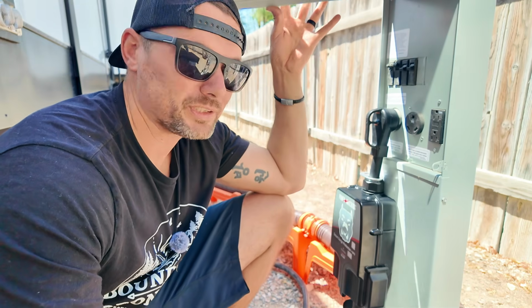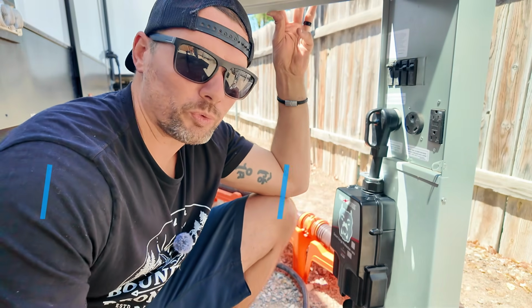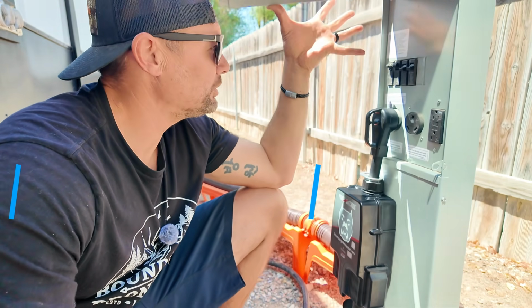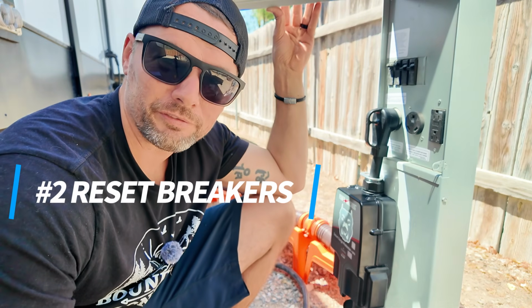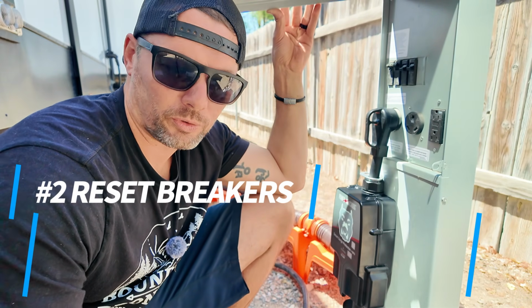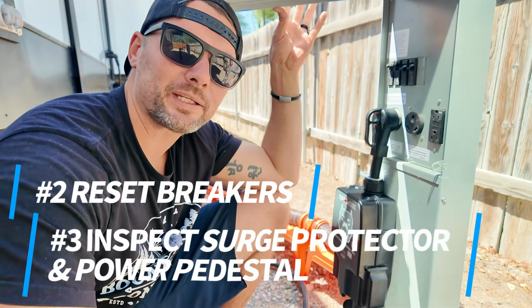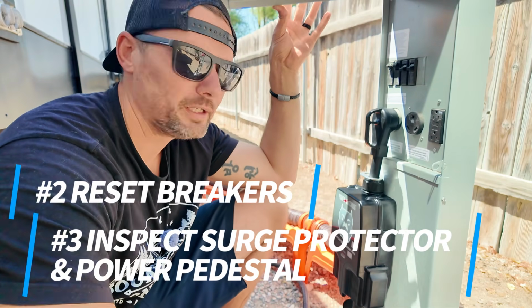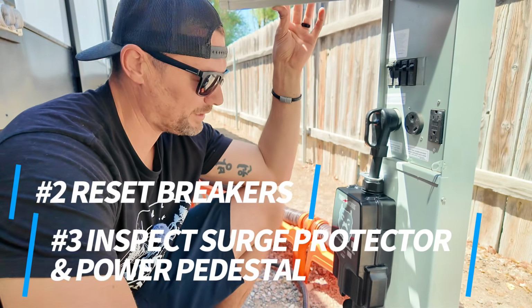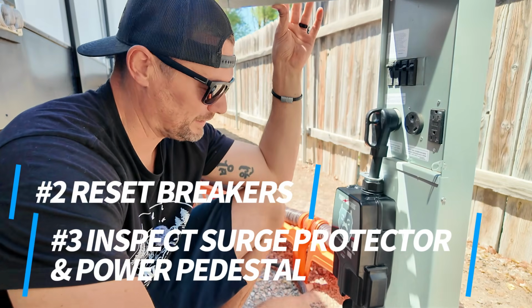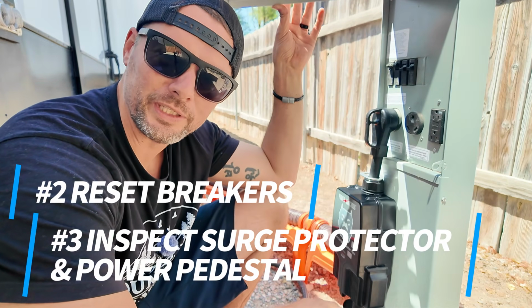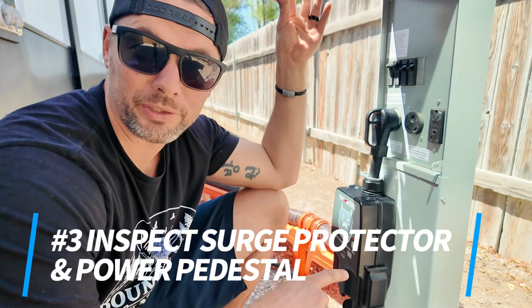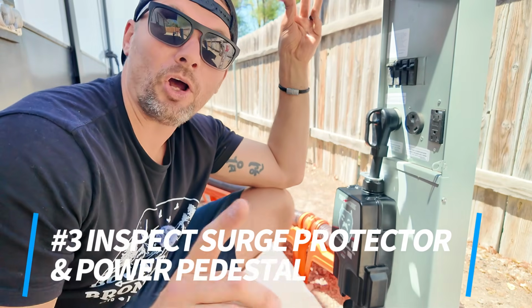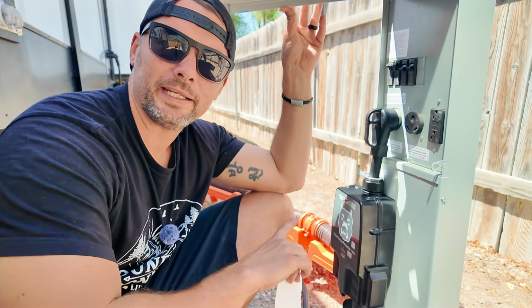Second, you're going to want to reset any of your breakers, maybe the breaker out here, maybe the ones inside your rig, and then come out and inspect your surge protector. Make sure that, in this case with Watchdog, you've got the white face, no error or fault codes, and that nothing actually burned up, because that could happen. That's super important to mention about the Watchdog, something none of the other ones I've seen do.